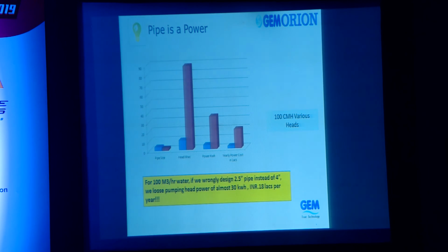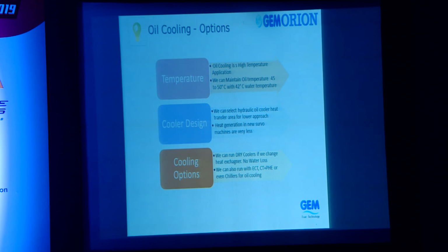So for a typical example of 100 meter cube flow, if we wrongly design a 2.5-inch pipe instead of a 4-inch pipe, we lose pumping head power of almost 30 kilowatt, which is about 18 lakhs per year, which is a hidden cost. So it is very, very important that pipeline sizes and pressures should be properly maintained for flow through all channels where we have cooling water.